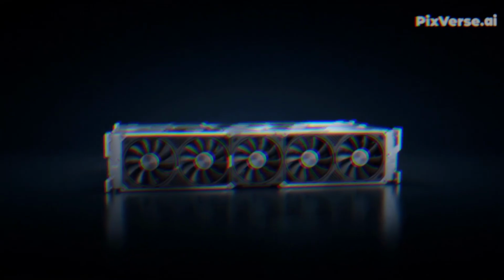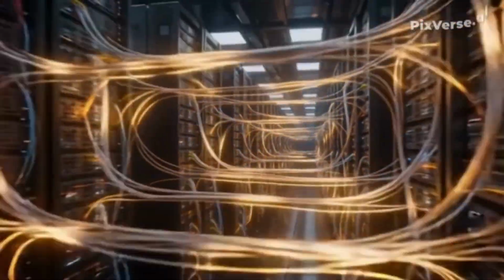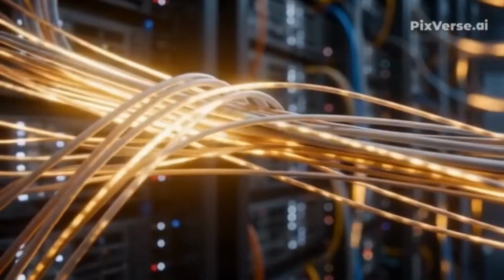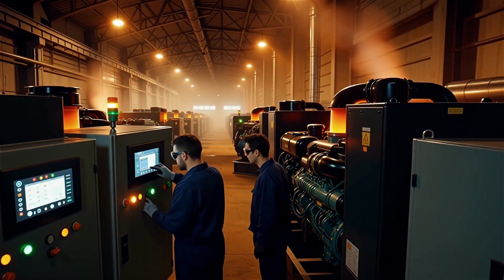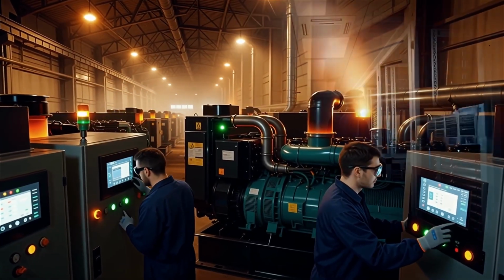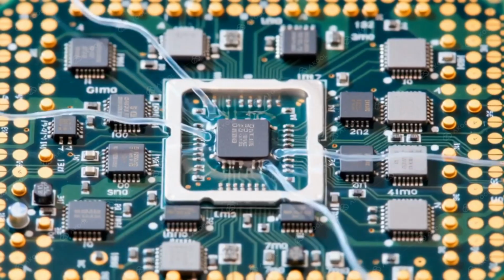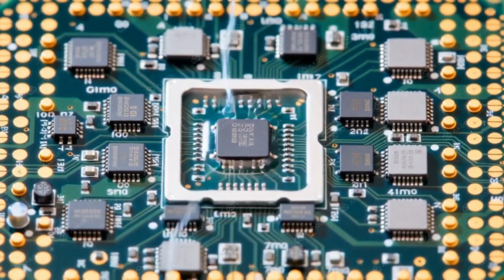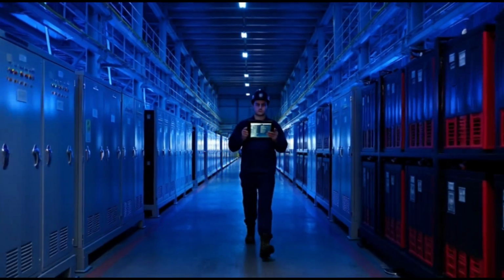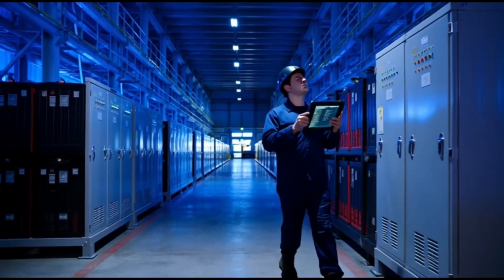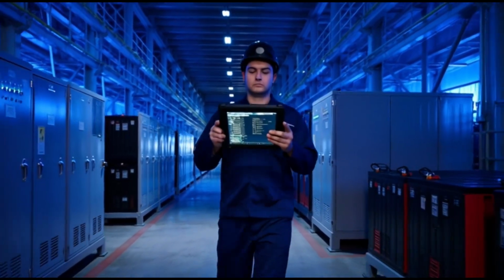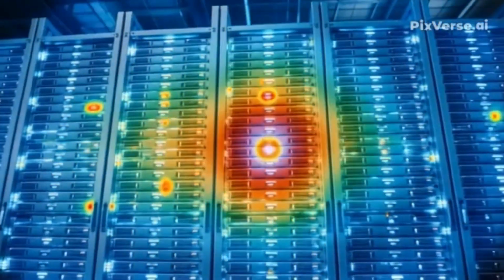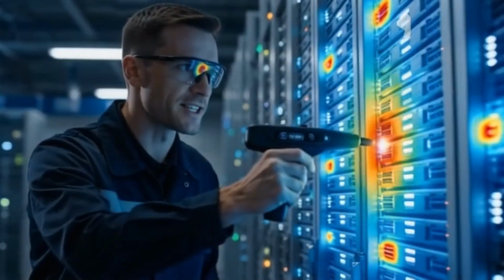A major data center may have dozens of generators, each one capable of powering hundreds of homes. This redundancy is not optional. Downtime for a hyperscale AI facility can cost millions of dollars per hour. The power systems are designed to tolerate the failure of any single component without the facility ever losing power. Engineers call this N+1 redundancy, meaning there is always at least one more backup than you need.